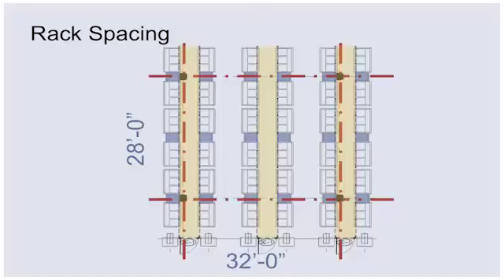This established a 14-foot module, so we developed a structural grid that's 28 by 32 feet. We used a 16-foot pitch for our hot aisle containment, allowing us to locate any diagonal bracing or other supporting structure within these hot aisles, since limited service would be needed there.